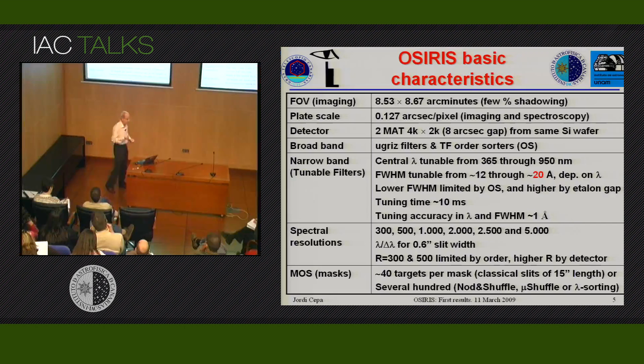Also, for these widths that are quite narrow, it's difficult to obtain a standard filter with a reasonable efficiency, especially in the blue, while in the tunable filters you can get quite high transmissions. The spectral response is another difference that you have to take into account. The peak is Gaussian and has some wings, while a good standard filter is more or less square, depending on the layers that you deposit on the filter.